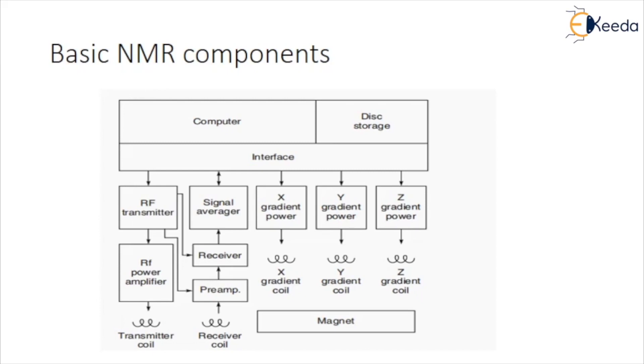The RF voltage is modulated with the pulse envelopes from the computer interface to generate RF pulses that excite the resonance. The pulses are amplified to levels varying from 100W to several kW depending on the imaging method, and are fed to the transmitter coil. The higher power levels are necessary for the large sample volumes encountered in whole body experiments.